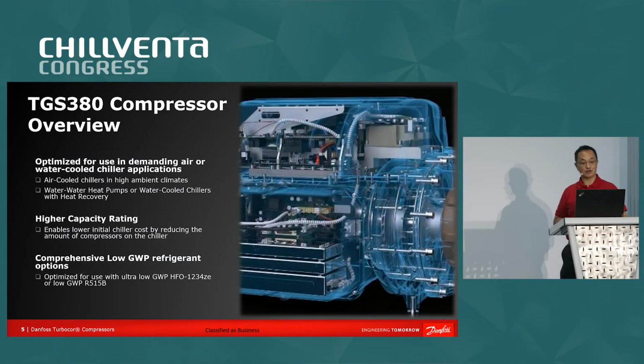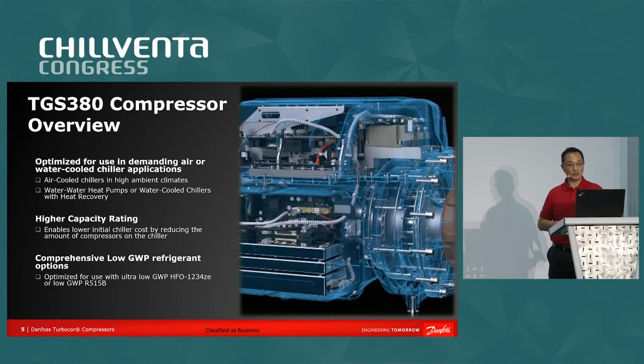Okay, so let's go ahead and get started. First of all, this new TGS 380 compressor is a brand new compressor that we will release by the end of this year, in just a few more months. This compressor is optimized for use in both air-cooled and water-cooled chiller applications. Specifically for air-cooled chiller applications, we've increased the operating map capabilities such that it can operate in very high ambient, high temperature environments. And we'll go into a little more detail about that.